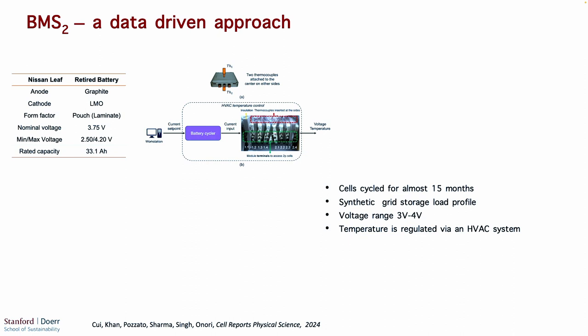Another characteristic we implemented was to derate the battery operation. Usually the voltage operation range is between 2.5 and 4.2 volts, the range those batteries can withstand. In the case of second life, we reduced that to 3 to 4 volts, because when you retire these batteries you need to be a little gentle and mindful about how you stress them, since they won't be as efficient or performant as they were in their first life.